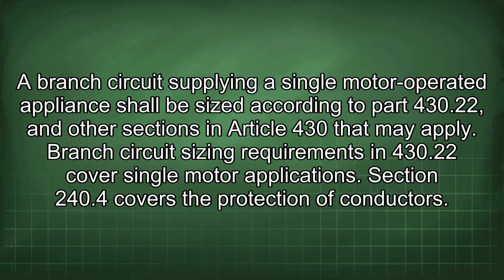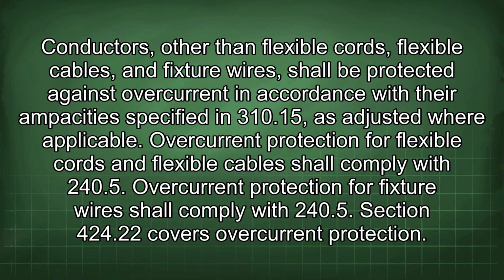Section 210.22(C) pertains to the permissible loads of a branch circuit. A branch circuit supplying a single motor-operated appliance shall be sized according to Part 430.22 and other sections in Article 430 that may apply. Branch circuit sizing requirements in 430.22 cover single motor applications. Section 240.4 covers the protection of conductors. Conductors, other than flexible cords, flexible cables, and fixture wires, shall be protected against overcurrent in accordance with their ampacities specified in 310.15 as adjusted where applicable. Overcurrent protection for flexible cords and flexible cables shall comply with 240.5. Overcurrent protection for fixture wires shall comply with 240.5.